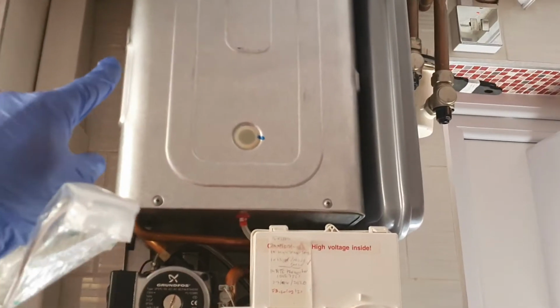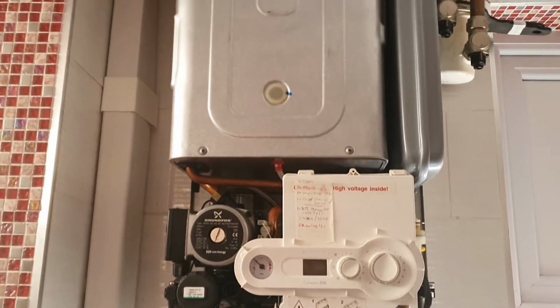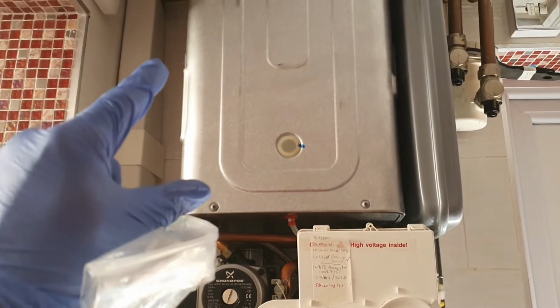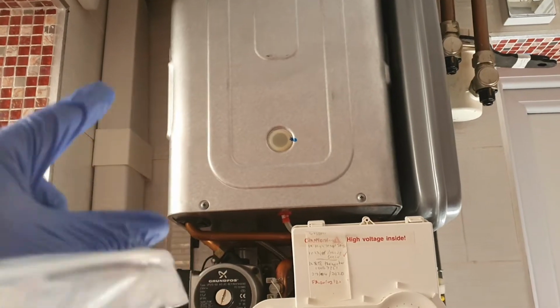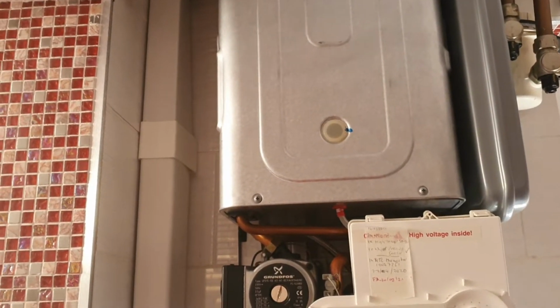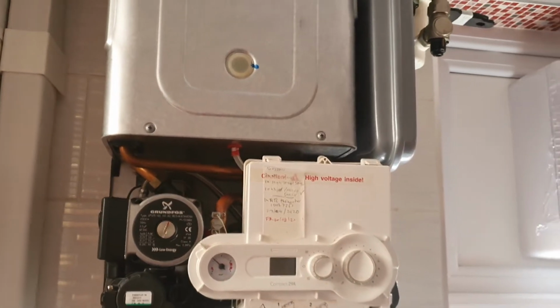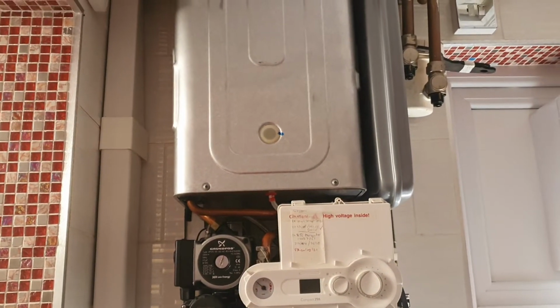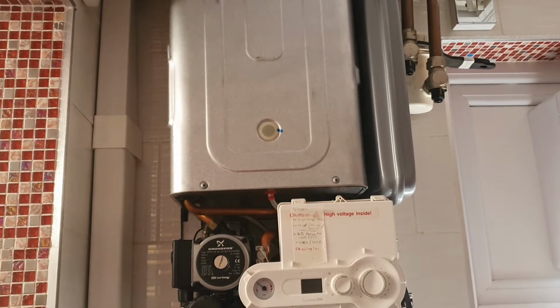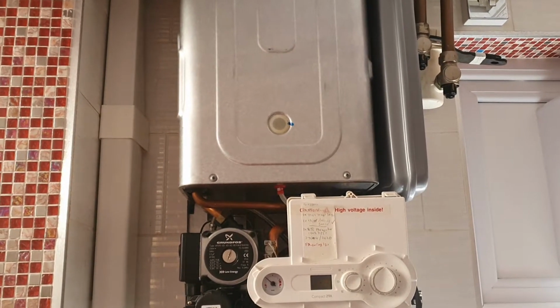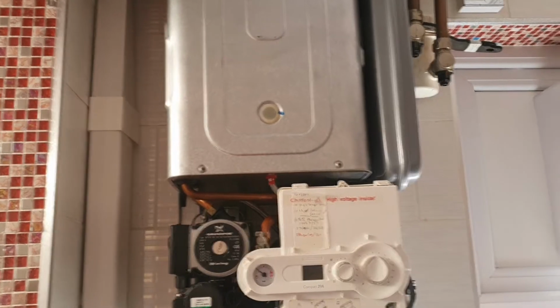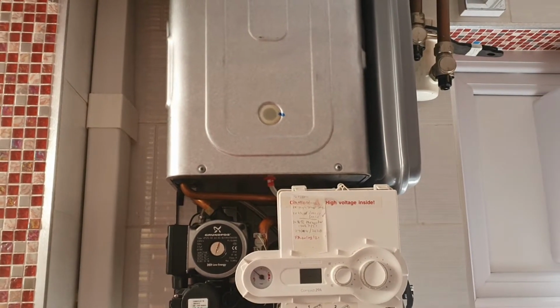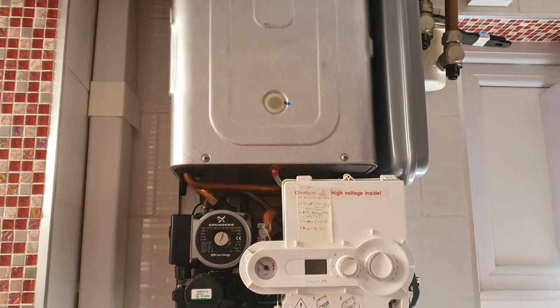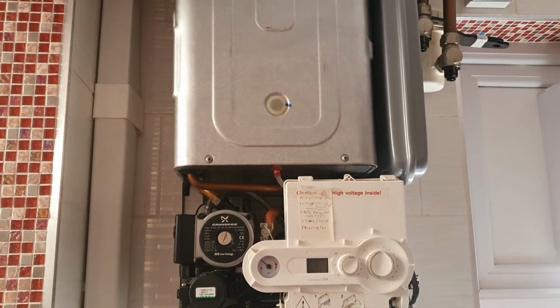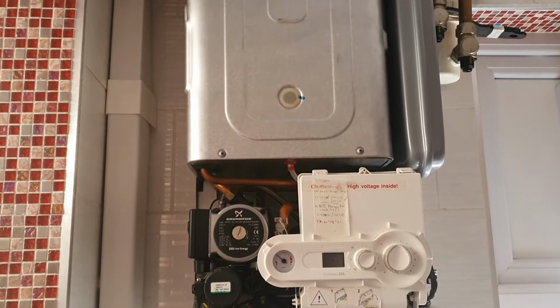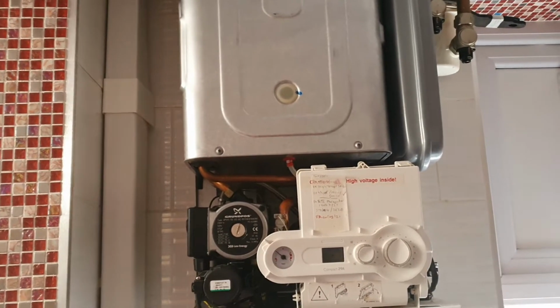We've been getting a banging noise on startup from the main exchanger, and it wasn't doing it all the time, it was occasional. So there's a couple of things to consider. First, the problem could be an issue with the main heat exchanger itself, which is rare but can happen. That also depends on the area you're in. We're in an area with soft water, so the chances of slime and blockage are minimal, but it can happen.